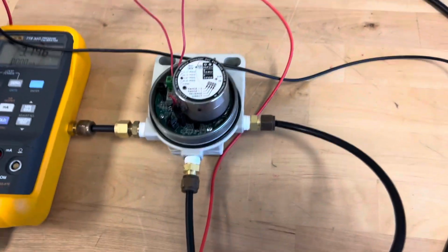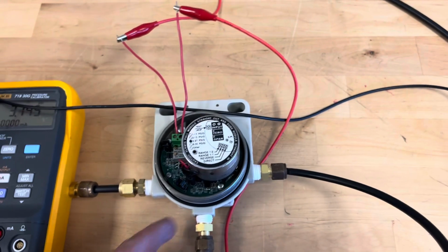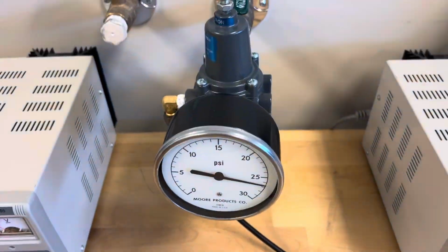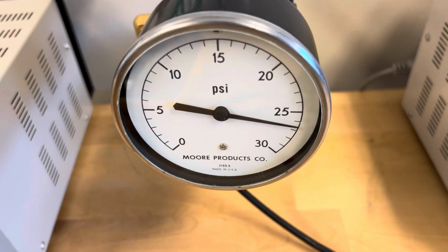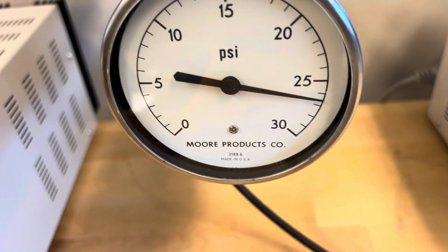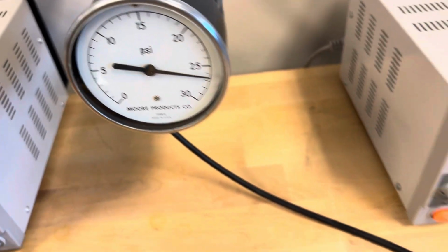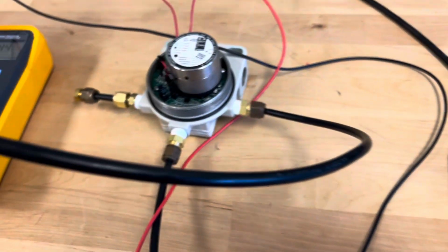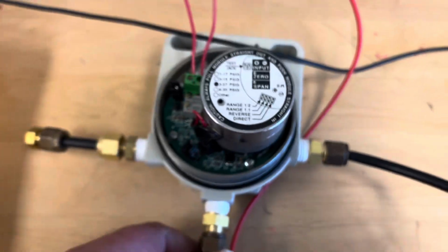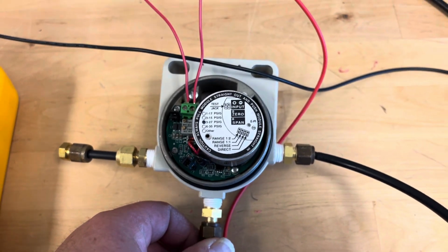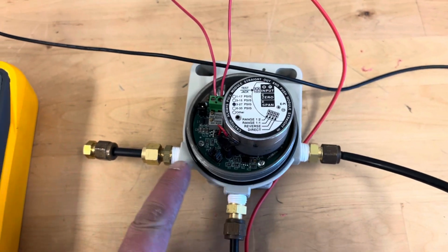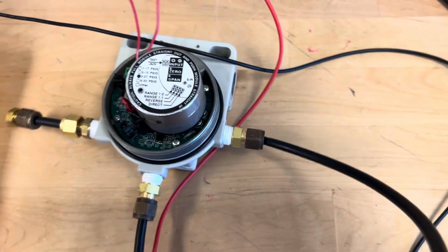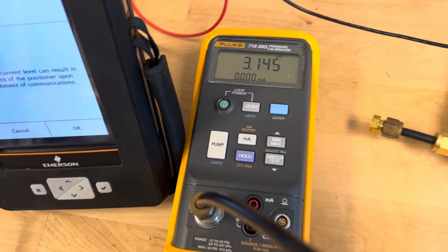Looking at my I2P transducer again here, what I have is wall supplied air with the regulator limiting it to 26 PSI, and I'm supplying that wall air into the input of the I2P transducer. And this one has two outputs. One here I have plugged off, and the other one is going to my Fluke meter.